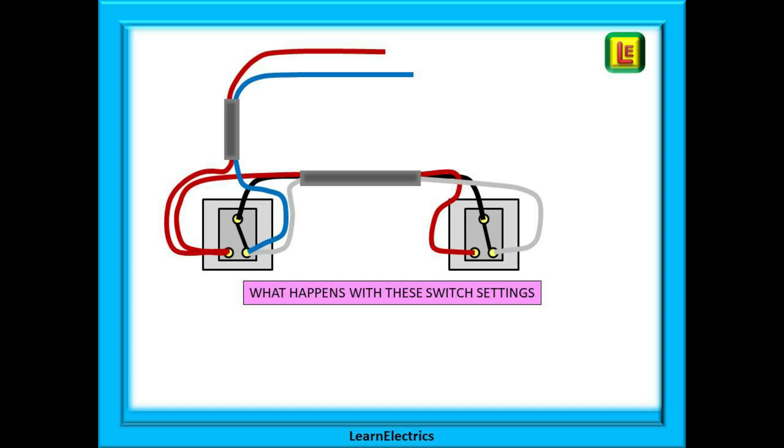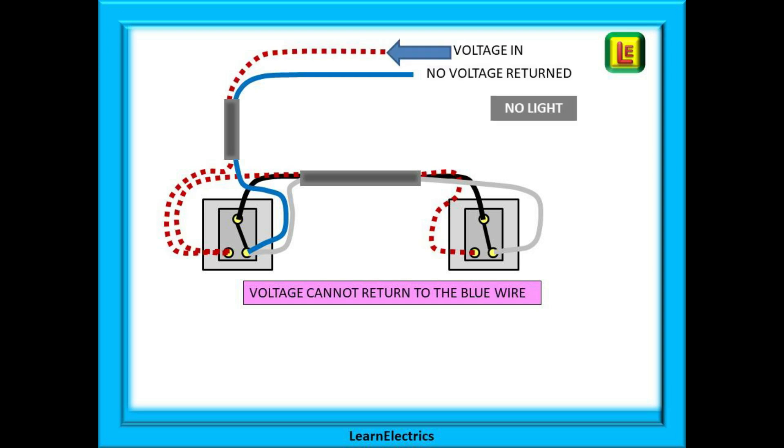What happens with these switch settings now? We have just put switch number 2 into the opposite state. Voltage will travel along the brown switch wire again to switch 1, L1, along the brown strapper wire to switch 2, L1, and there it stops. The voltage cannot reach the black strapper wire. No voltage is returned so the light goes out.